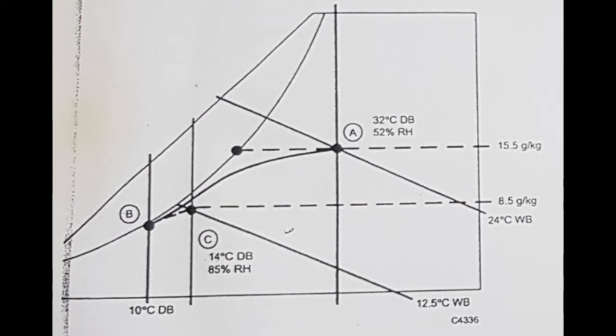Point number three: The leaving air is at 14 degrees centigrade dry bulb and 85 percent RH, that is point C. The moisture content is 8.5 grams of moisture per kilogram of dry air. The moisture removed is 15.5 grams per kilogram minus 8.5 grams per kilogram, which equals 7 grams of moisture per kilogram of dry air.